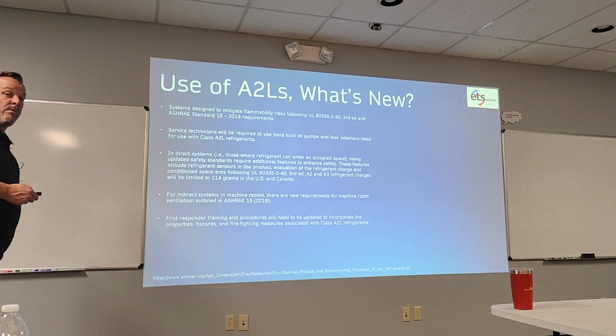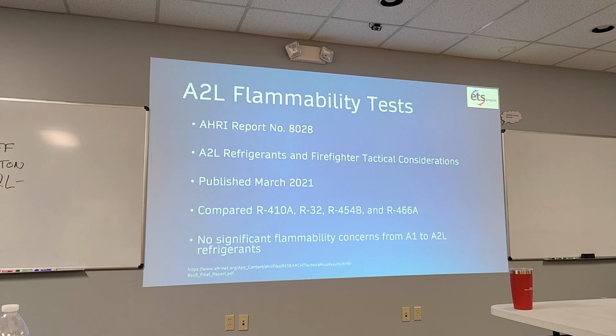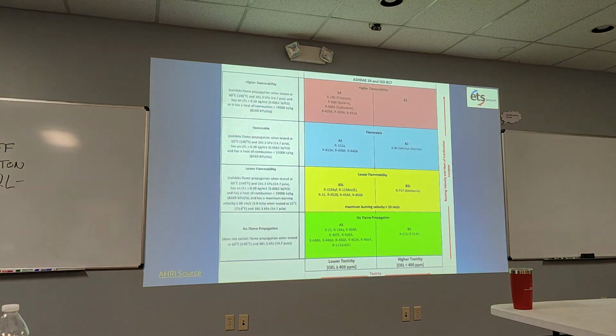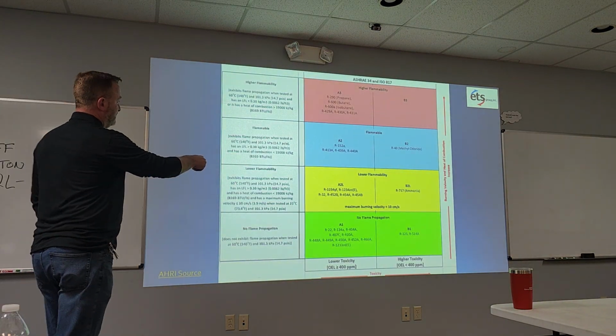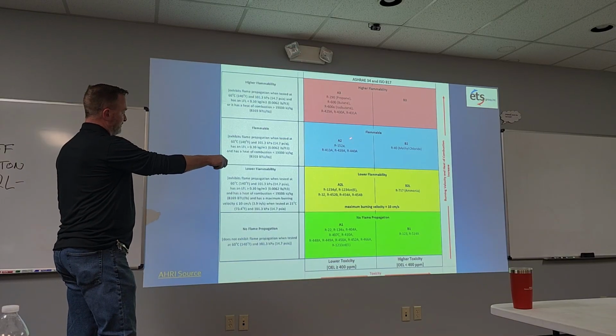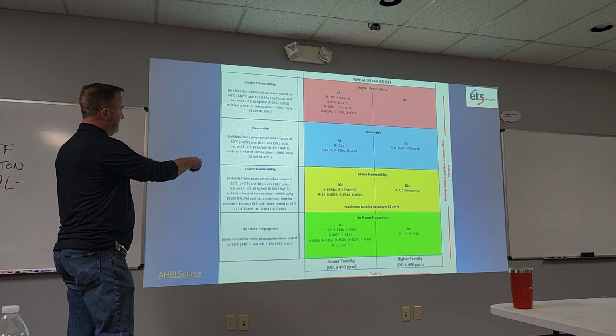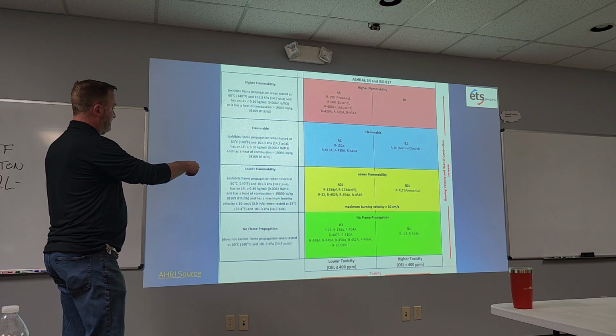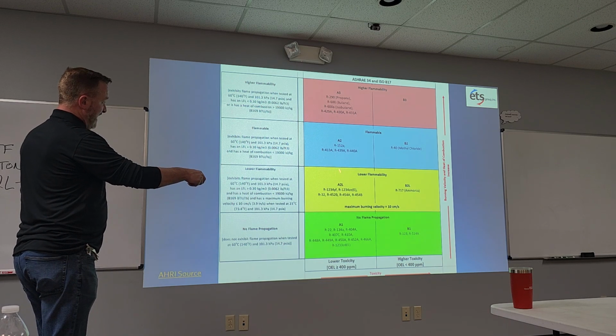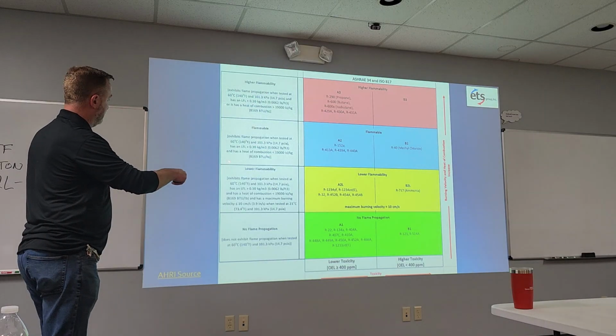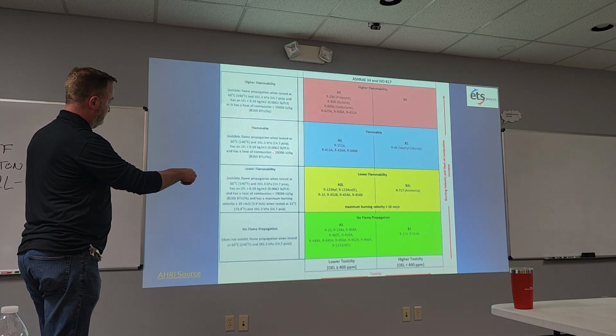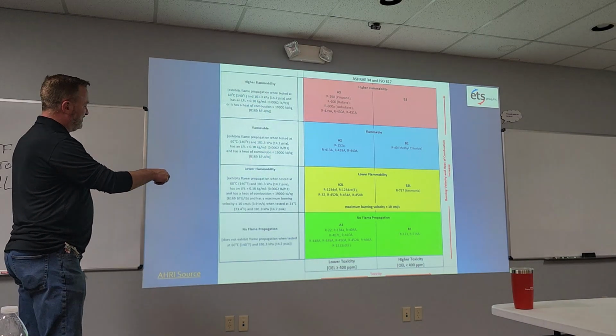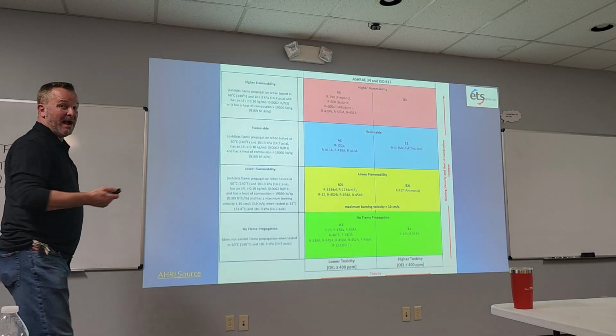Jeff, what's the difference between A2 and A2L, and how do you designate that? Lower flammability. A2L is low. They're both flammable, but A2 exhibits flame propagation when tested at 140 degrees, has an LFL of 10 or greater, and a heat of combustion of 8,169 BTU per pound.